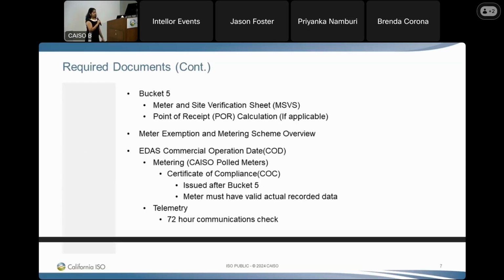So after the point-to-point test, for the bucket 5, we require a MSVS, meter and site verification sheet. This document has a lot of information, which is really crucial for the site to receive a COC, Certificate of Compliance. So the information on this is required for us to complete the meter data validation. And multiple parties may have to enter the information, so a lot of coordination is also needed so that accurate information is given to ISO on the MSVS sheet.